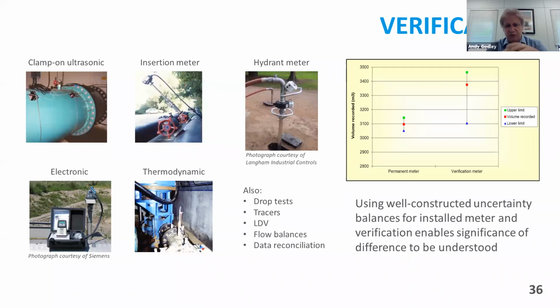But the important thing to remember about electronic verification is that it's not actually giving you an independent measurement of the flow, as the other techniques shown there are. What it's doing is looking at the meter electronics, and trying to diagnose whether those meter electronics are behaving as they should, as they were when the meter was performed. That all the circuitry within the meter electronics are still behaving as they were when the meter's manufactured.